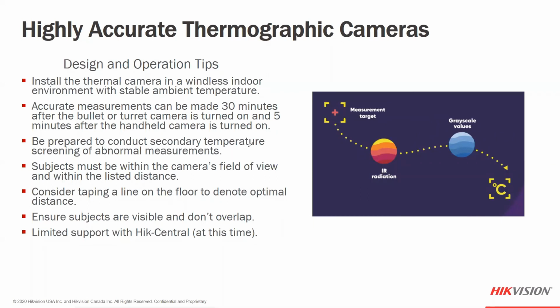And we do recommend that they walk in through a queue or an area, maybe a turn to the right or turn to the left as they walk in, and walk past the camera. There is some warm up time. The camera does have to acclimate to its environment. So we have about 30 minutes for the camera to warm up, to adjust its own operating temperature to the ambient temperature and the background measurements that it's actually making, and it increases its accuracy level. So with 30 minutes to start that warm up period before you can start calibrating and making those accurate measurements. We also have 5 minutes for the handheld device, we want to allow that to warm up for about 5 minutes.